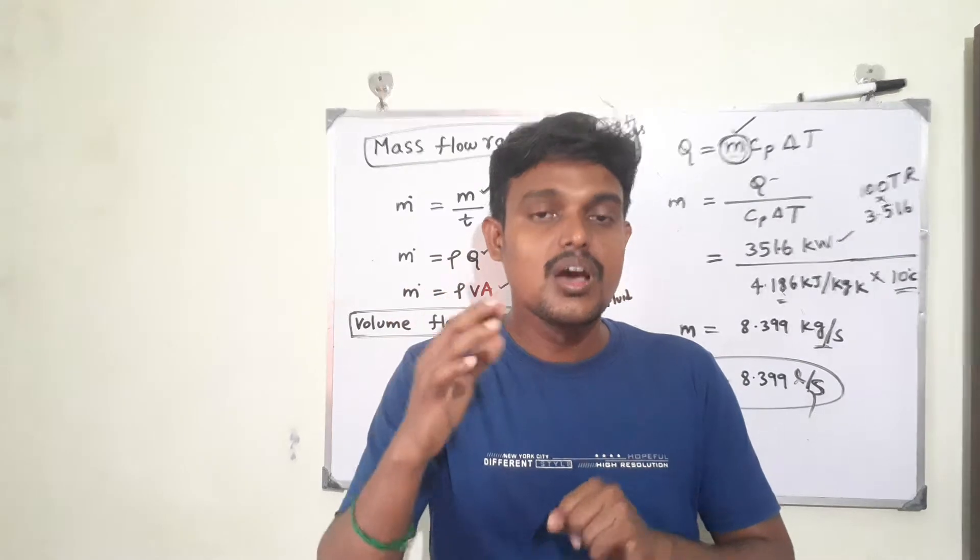We will call this a high delta T. In the same way, in another scenario, if your delta T is coming below your design delta T — for example if I am getting the temperature between the chilled water in and out as 5 degrees Celsius, but the design delta T is 10 — it means that it is a low delta T. If your chiller system is running with low delta T for a long time, you will be getting a lot of problems in your chiller system and you are losing your energy.